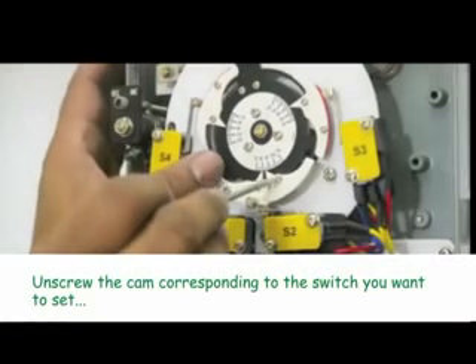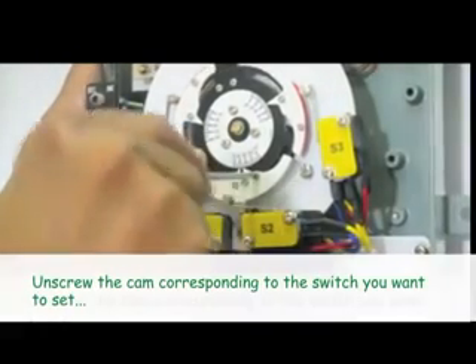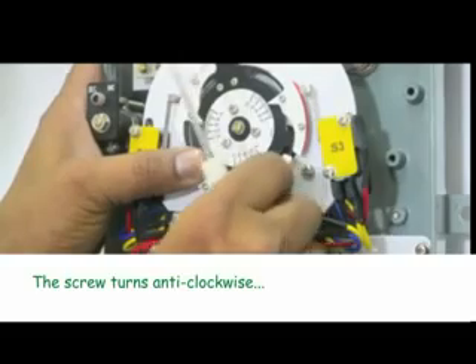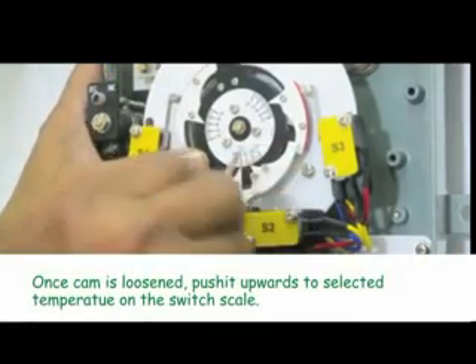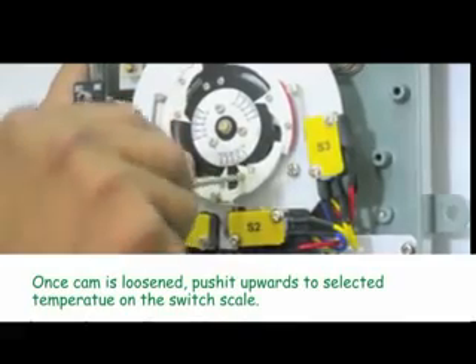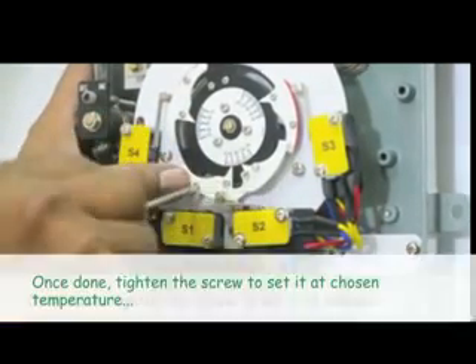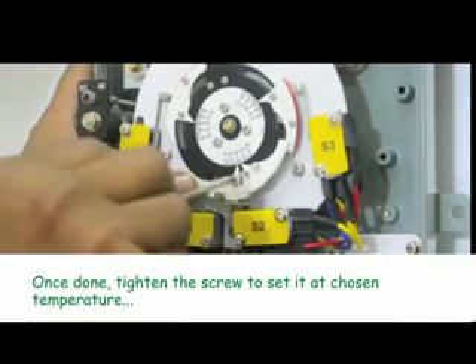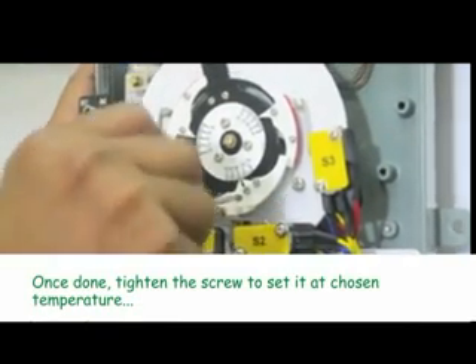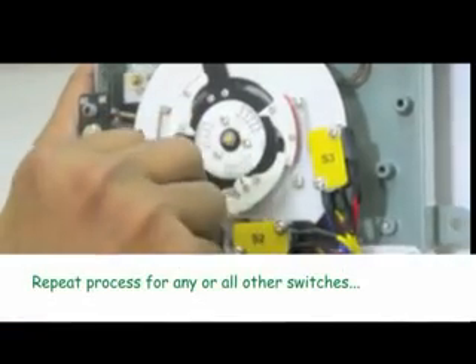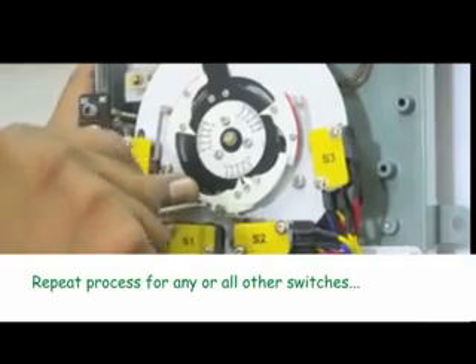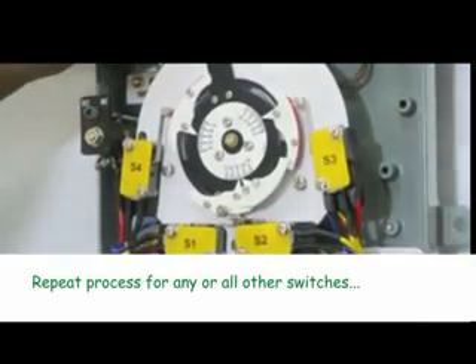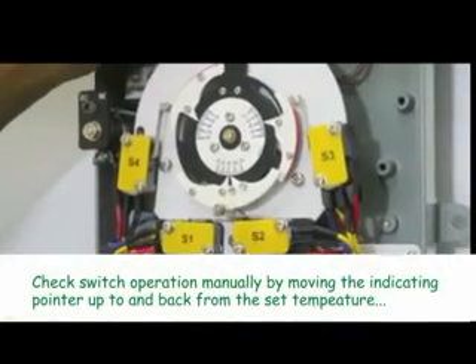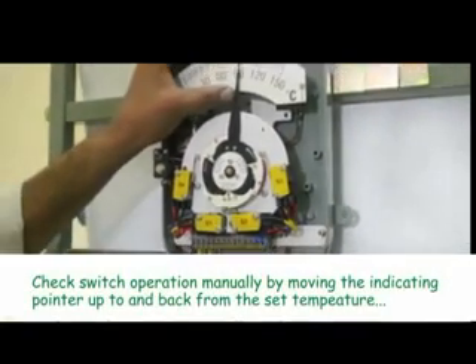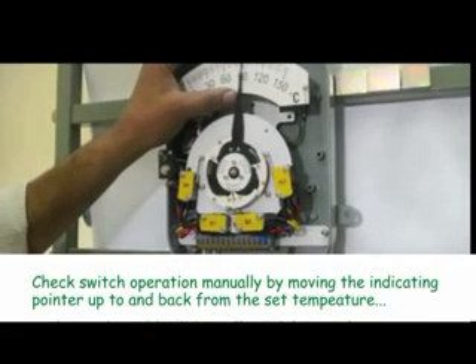Switch setting procedure. Unscrew the cam corresponding to the switch you want to set. The screw turns anti-clockwise. Once the cam is loosened, push it upwards to select the temperature on the switch scale. Once done, tighten the screw to set it at the chosen temperature. Repeat the process for any or all other switches. Check switch operation manually by moving the indicating pointer up to and back from the set temperature.